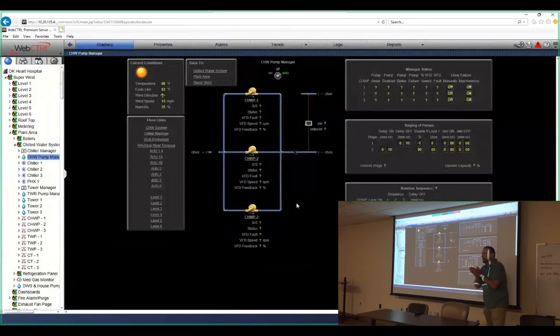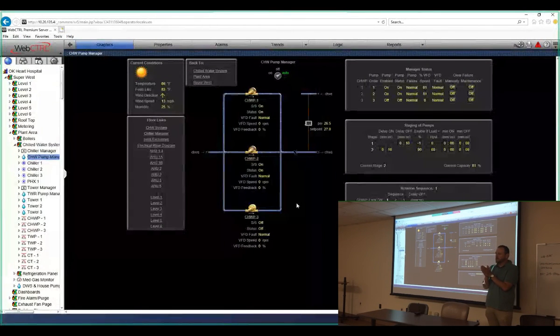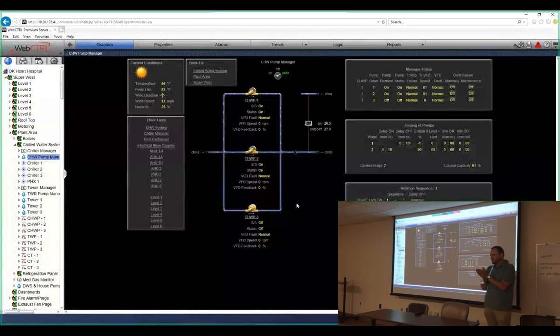So the system's broken up in the plant. It's broken up by the different pieces that need to be managed. In other words, your chill water pumps rotate, your condenser water pumps rotate, and your chillers rotate. So those chill water pumps are handled as a separate system, and we manage their rotation and who needs to be on at different times. If you click down here, click on this manual rotation, there's the option of rotating the pumps.